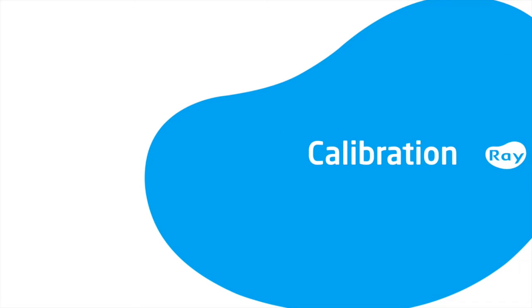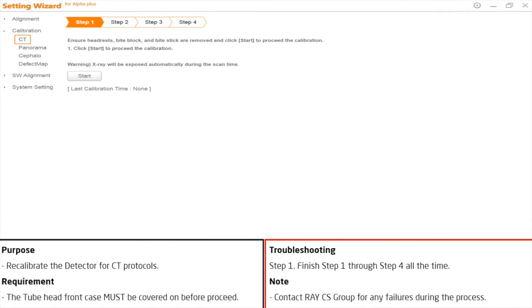The sensor might be recalibrated on site, since the temperature and humidity change during shipping. Make sure you don't leave any parts on the chin rest module. Also, the tube front case must be covered before proceeding.